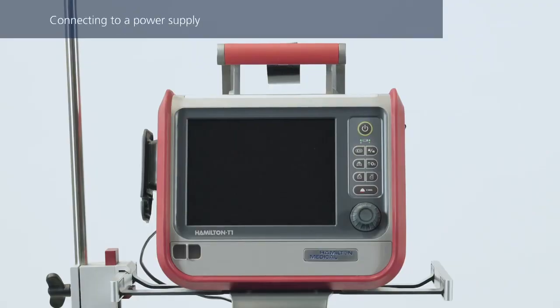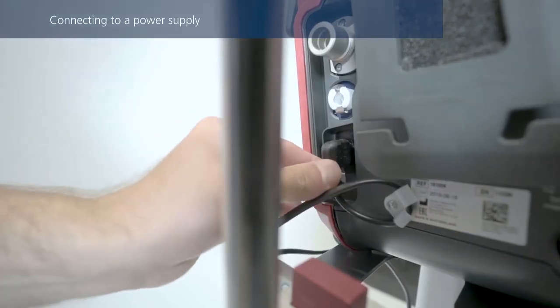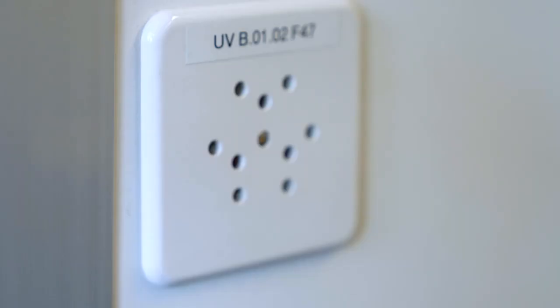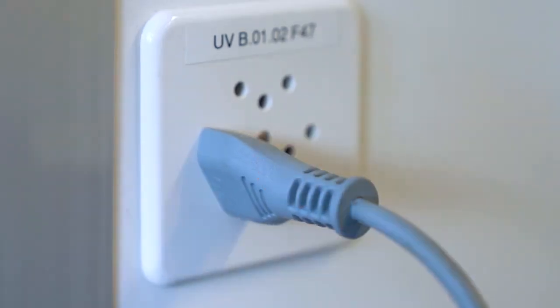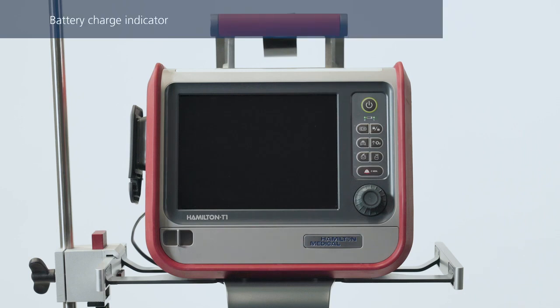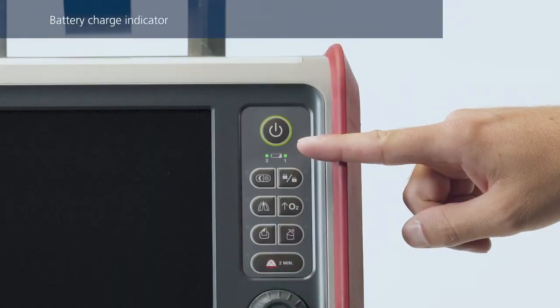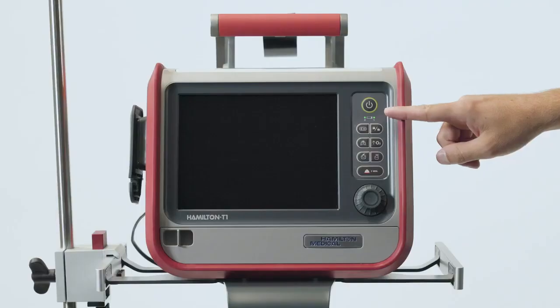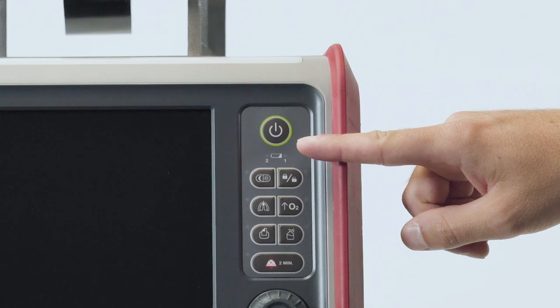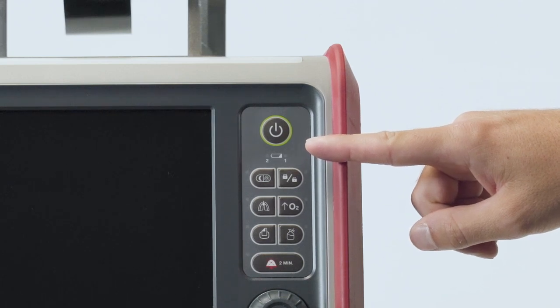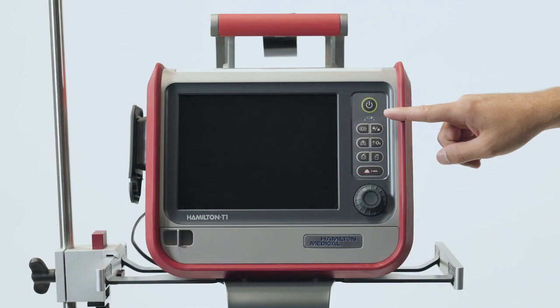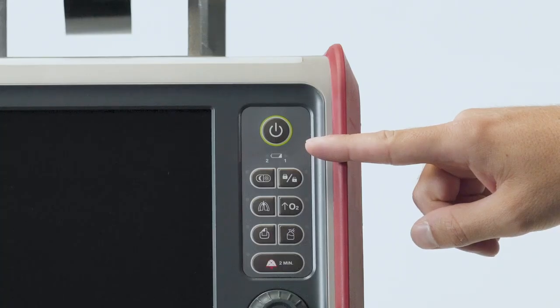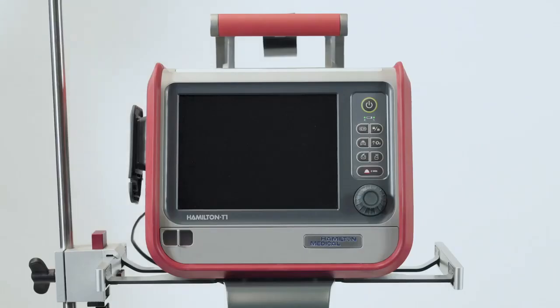Check the power cable is securely in place to make sure it can't disconnect accidentally, and then connect it to the primary power outlet. The battery charge indicator is solid green when the battery is fully charged and connected to primary power, even when the ventilator is turned off. If the indicator is flashing, this tells you the battery is still charging. If the battery is not charging, for whatever reason, the indicator will stay dark. Make sure the ventilator is connected to a power source before you start ventilation.